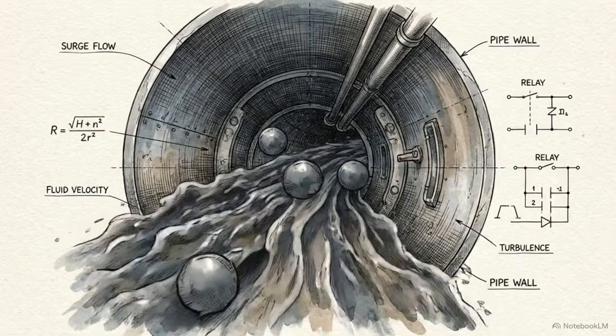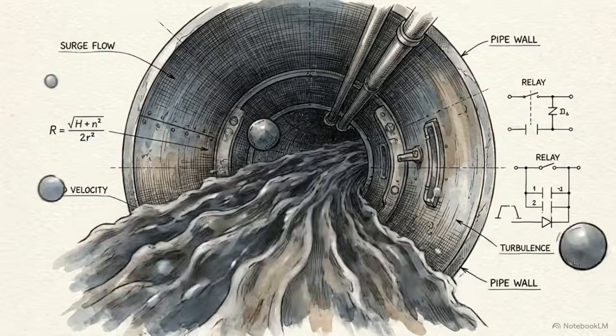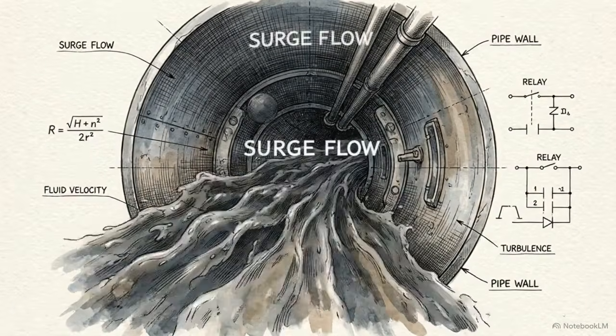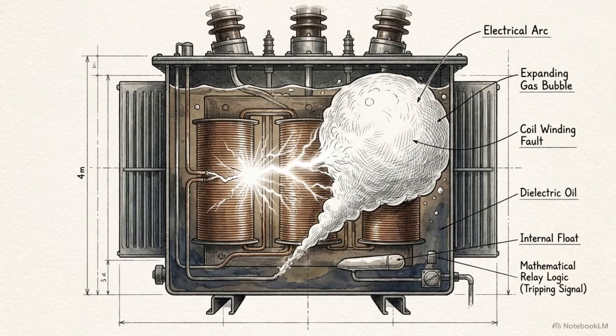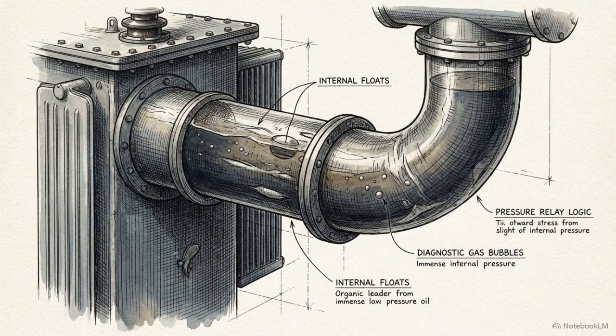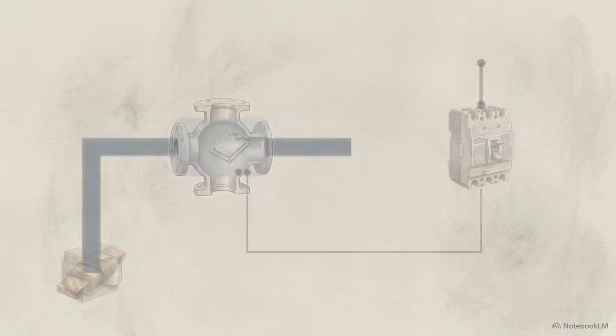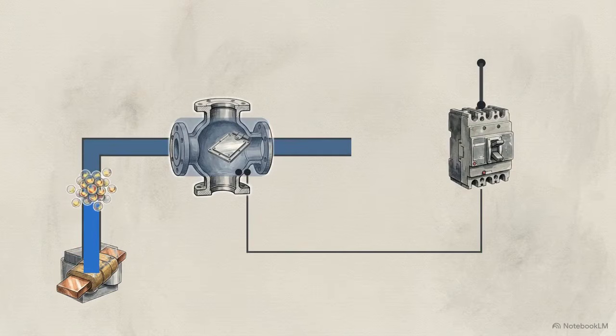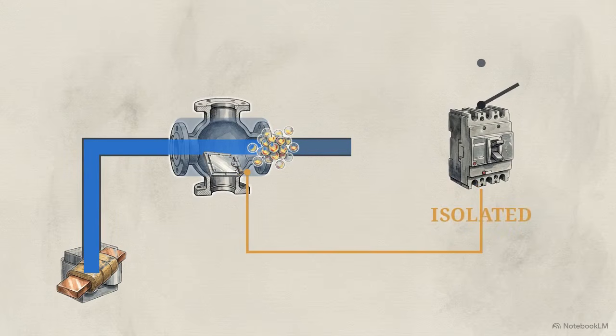But not all failures are slow. When a massive internal electrical arc occurs, the resulting chemical reaction is explosive. The sudden electrical arc causes rapid, violent gas expansion inside the tank. This creates a high-velocity physical wave of oil that surges aggressively up the pipe toward the conservator. In this schematic of the Buchholz relay, the rushing wall of oil strikes a lower flap. The force pushes the flap down, closing a trip circuit. This signals the main circuit breakers to open, isolating the transformer before internal pressure causes a catastrophic explosion.